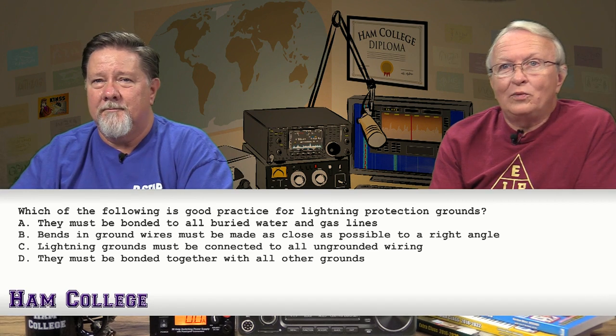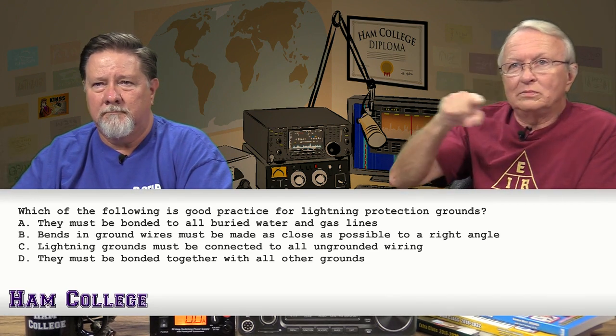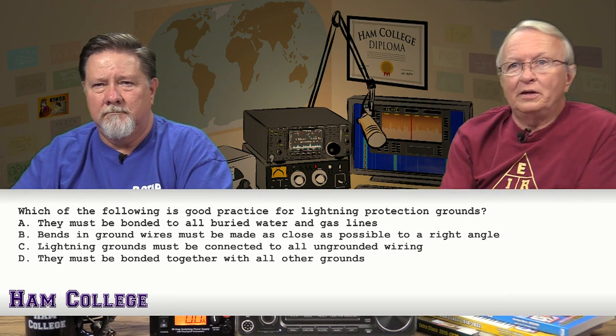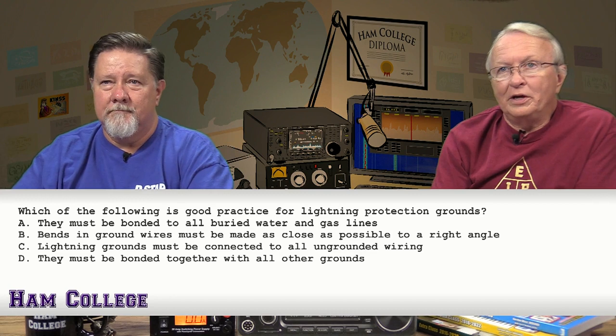Bends in ground wires must be made as close as possible to a right angle, a 90-degree angle - no, as a matter of fact, that's the right opposite of what you want. You want your grounds to be as straight as possible to the ground connection. You want to avoid using right angles.